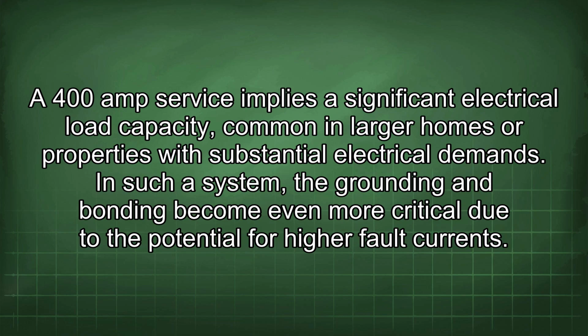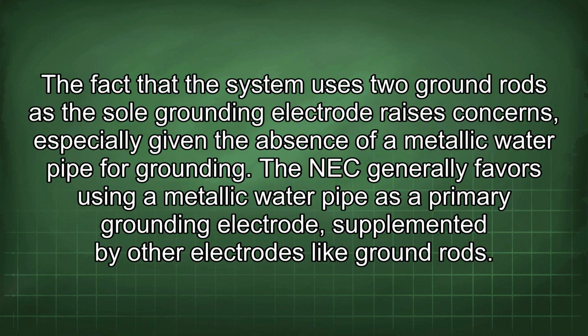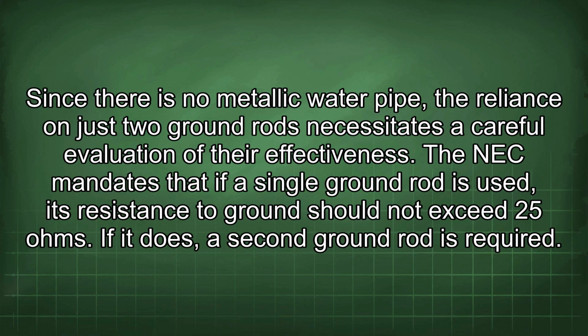In such a system, the grounding and bonding become even more critical due to the potential for higher fault currents. The fact that the system uses two ground rods as the sole grounding electrode raises concerns, especially given the absence of a metallic water pipe for grounding. The NEC generally favors using a metallic water pipe as a primary grounding electrode, supplemented by other electrodes like ground rods. Since there is no metallic water pipe, the reliance on just two ground rods necessitates a careful evaluation of their effectiveness. The NEC mandates that if a single ground rod is used, its resistance to ground should not exceed 25 ohms. If it does, a second ground rod is required.